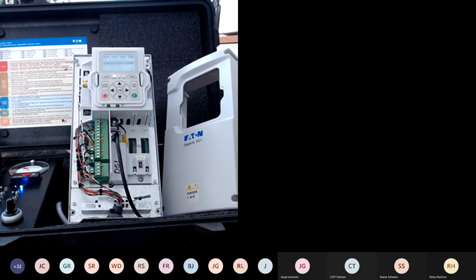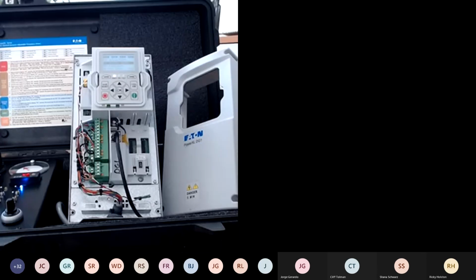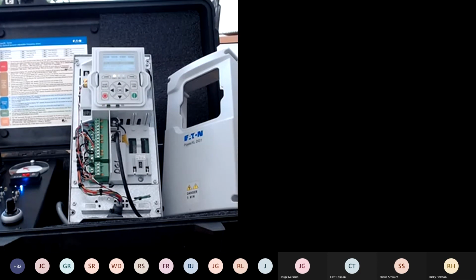If there's anything else other than harmonics that we can discuss, I know there are some great bypass applications. We talked about the ways you can bypass a VFD. That's through an across-the-line starter. You can bypass through a reduced voltage starter, and you can also bypass with a redundant drive application. So, other things that the team can think of here? I know we have a few minutes left.